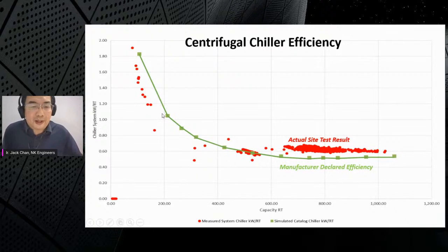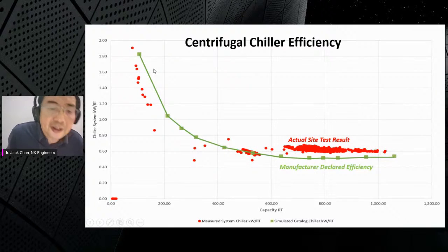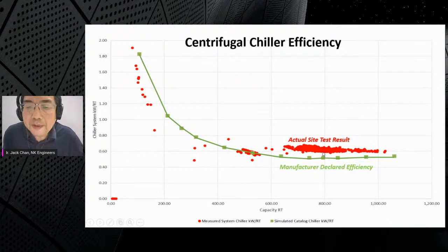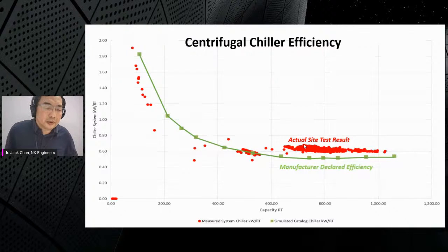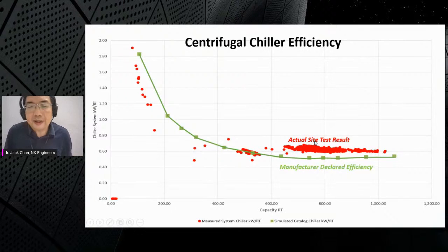Just now we tested the chiller at the factory. When you do an actual site test, the site test must at least mirror what is declared by the manufacturer. Everything must be mirrored. For example, over here it is low, yes, it's low. Over here it is high, yes, it's high. So it must mirror. The other thing you have to find out is the deviation from the actual test to the manufacturer's declared efficiency. If you find that all these values are much higher, then you can ask the manufacturer to come and either reassemble the chiller, or in the worst case replace the whole chiller, until you get the efficiency that you require.